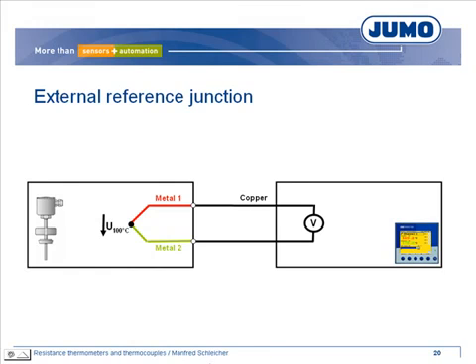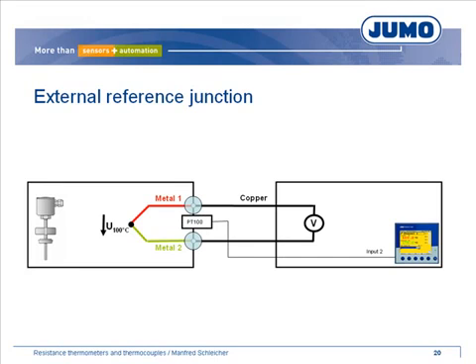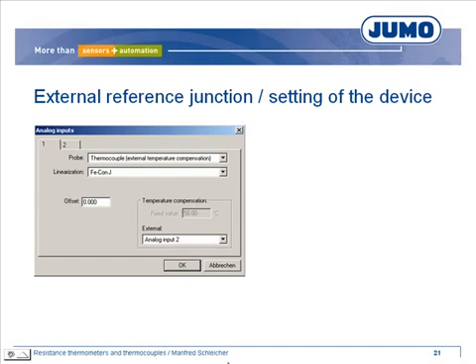Generally, thermocouples and field devices can be connected using a copper wire. In that case, the reference junction is on the terminals of the thermocouple. The device measures the voltage of the thermocouple minus the voltages of the terminals and calculates the temperature differential. To identify the process temperature, the temperature differential and the temperature of the terminals must be added up. The field device measures the temperature of the terminals using a further temperature sensor, for example a PT100 connected to input 2. Select external temperature compensation for the thermocouple input and choose the input for the reference junction temperature.